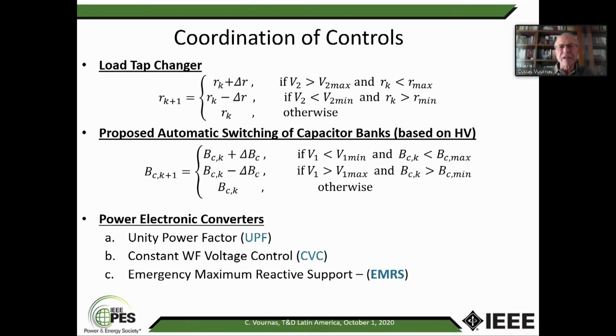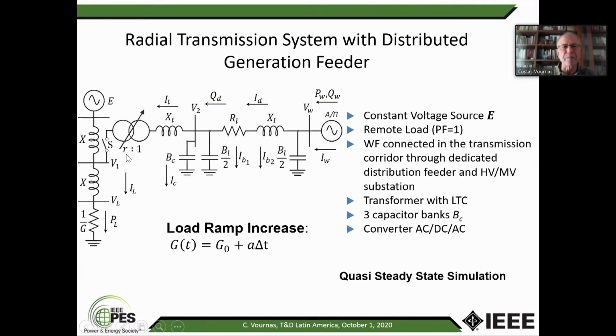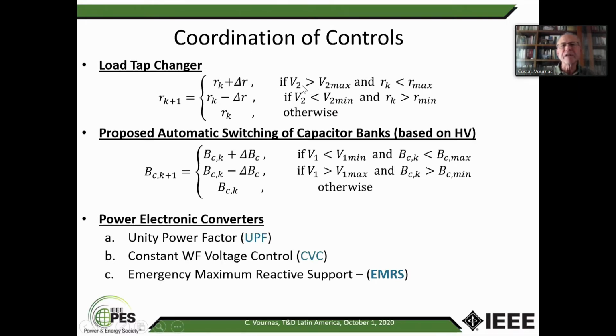So the controls that are available on the wind farm feeder are, first of all, the load tap changer. So you saw the R here is the ratio on the primary side. And you see if the voltage is above a dead band and I still have steps of taps to change, I increase the tap, because by increasing the tap on the primary, I drop the voltage in the secondary. So if the voltage in the distribution side is above its deadband, then the tap ratio is increased. On the other hand, if the voltage in distribution is below the deadband, then the tap on the primary is decreased. If it is inside the deadband, then the tap remains where it is.